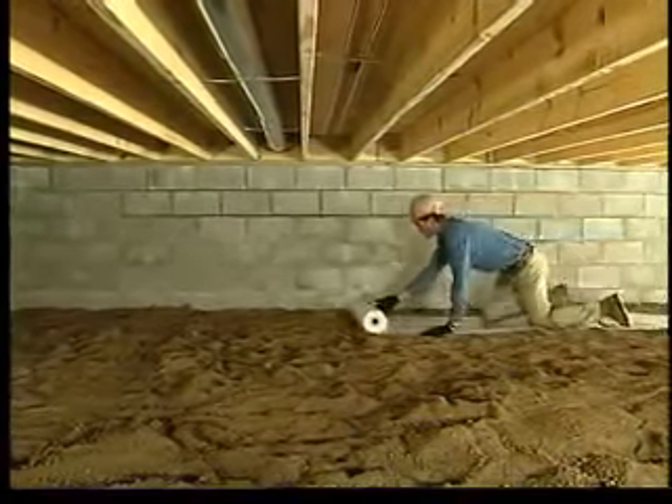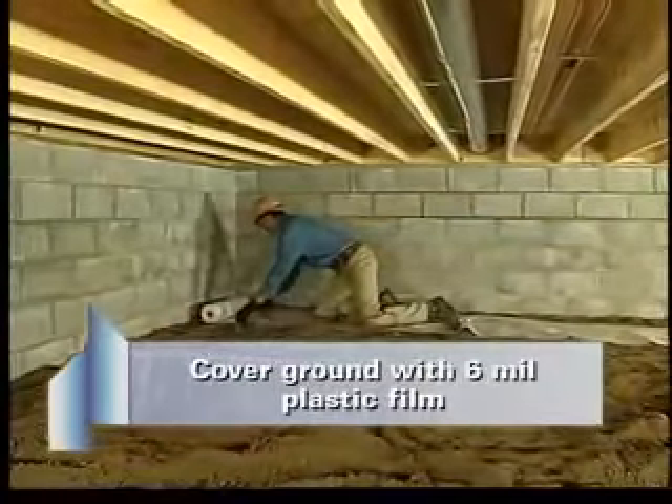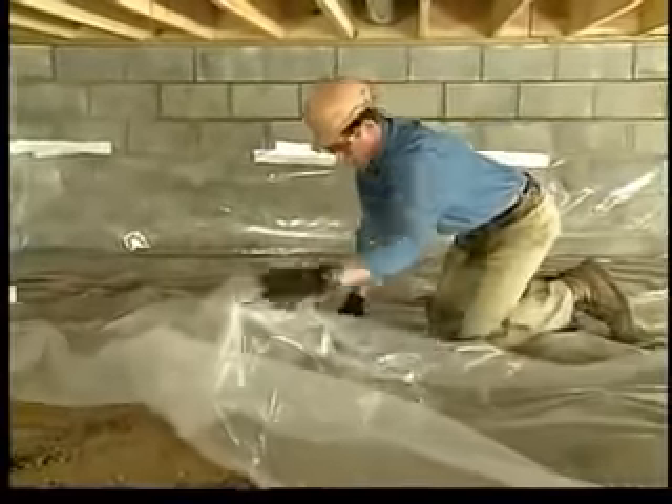Usually, before any insulation is installed in either vented or unvented crawl spaces, the ground should be covered with sheets of 6 mil plastic film. The sheets should overlap each other by approximately 12 inches and extend a few inches up the walls.